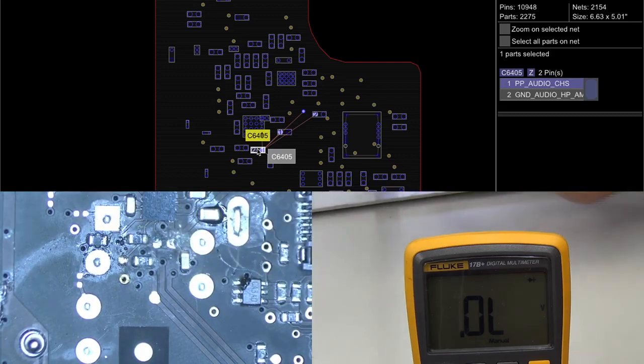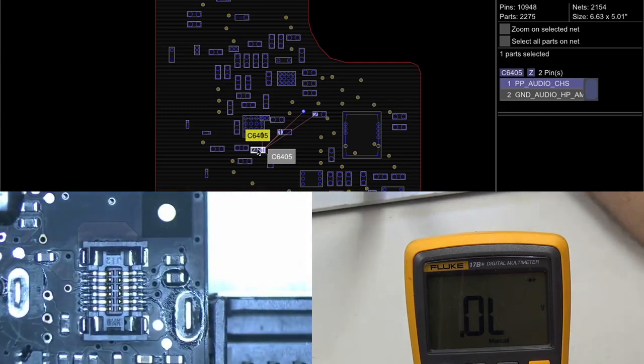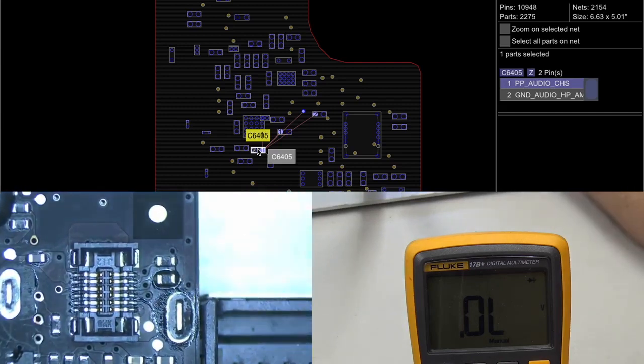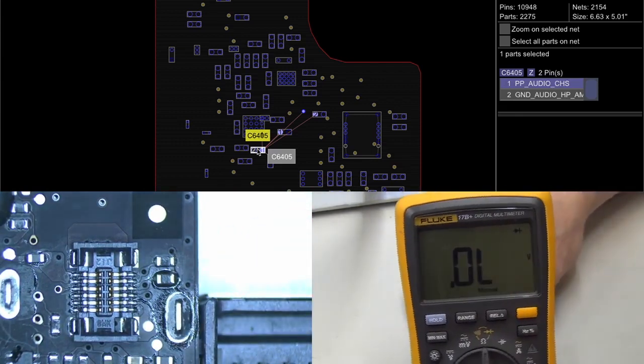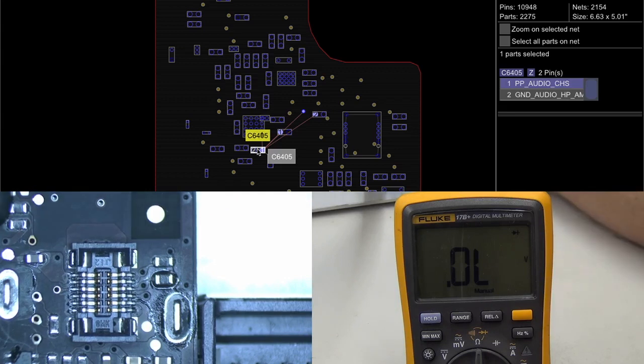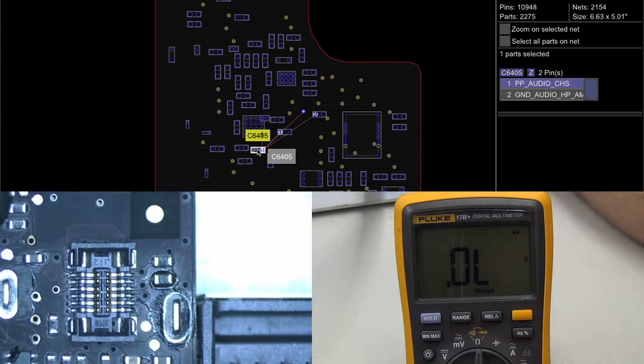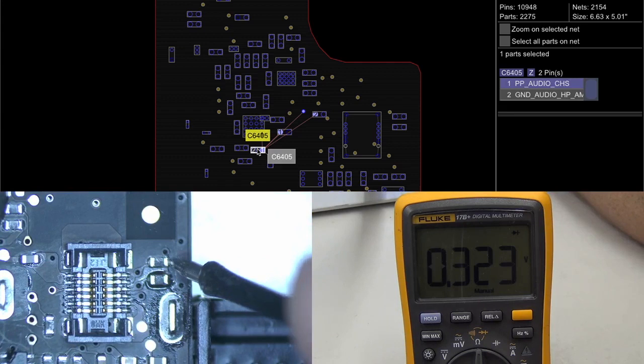Alright, that component has been removed. Remember before we measured our 3.42 volts from these two places? Let's see if we have a short to ground now. We still have it on resistance mode. Red probe on ground, black probe measure here. And look, we're getting 0.323 now, so we're no longer having a short to ground. We have removed the short to ground.